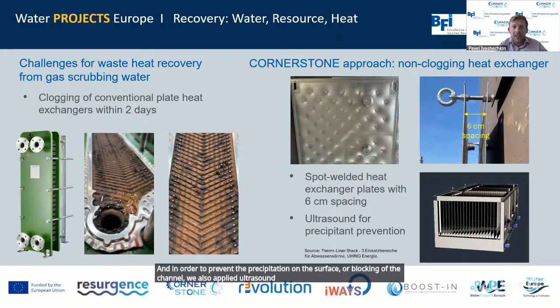Since we didn't have access to a direct reduction plant, we first tried with a gas scrubbing water channel of a blast furnace. On the left side you see we had quite a layer—after 20 days, around 8 mm, and the heat transfer was reduced by 90%. Actually, already after 5 days, we had only half of the energy we could recover.